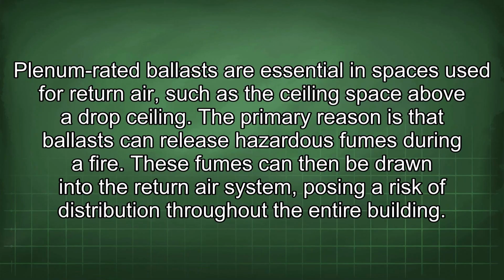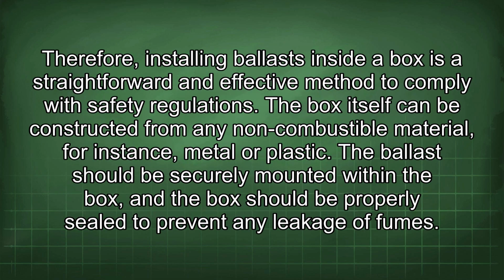Plenum-rated ballasts are essential in spaces used for return air, such as the ceiling space above a drop ceiling. The primary reason is that ballasts can release hazardous fumes during a fire. These fumes can then be drawn into the return air system, posing a risk of distribution throughout the entire building. Therefore, installing ballasts inside a box is a straightforward and effective method to comply with safety regulations.